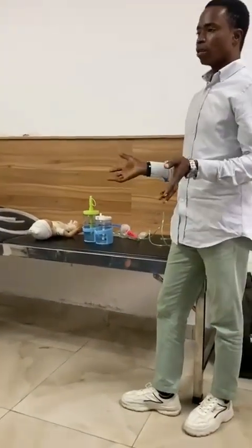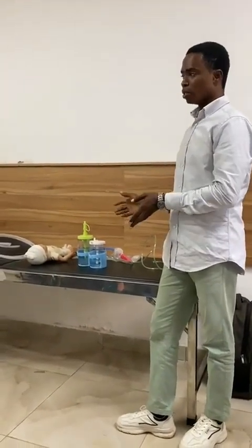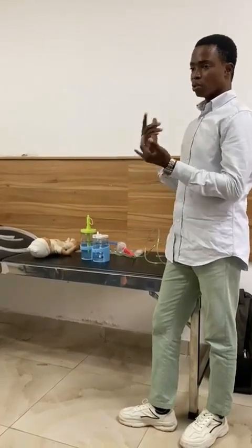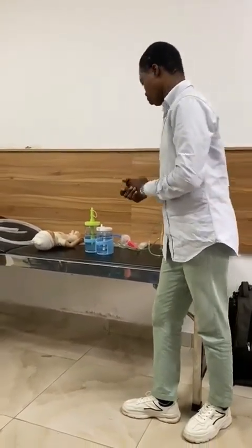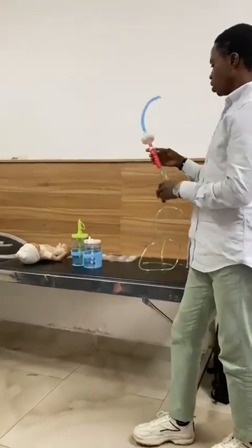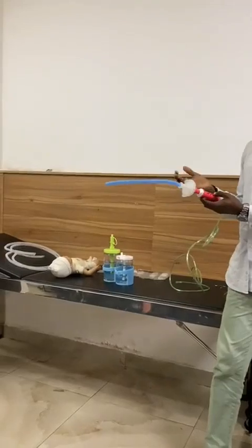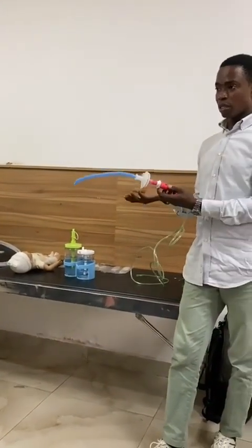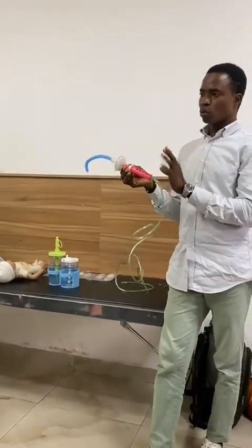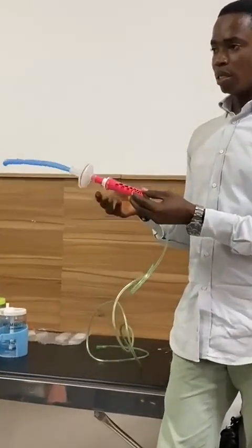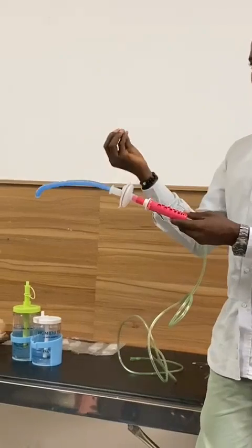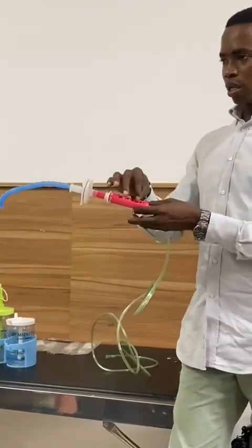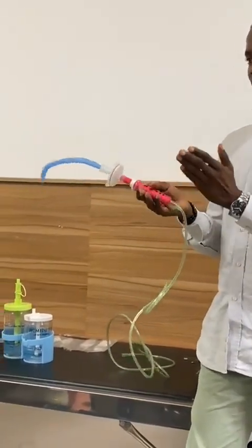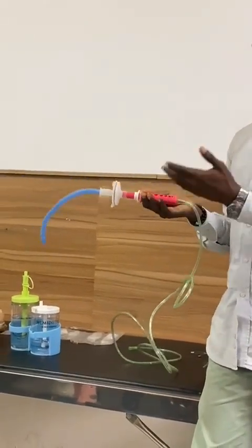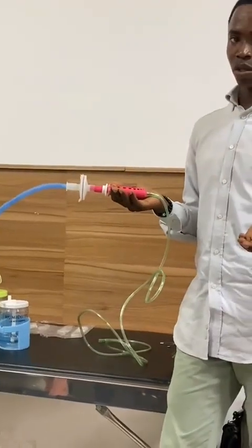As compared to other kinds of CPAP that use electricity and need an air compressor, this does not require electricity. All you need is an oxygen source. You can use an oxygen cylinder or an oxygen concentrator. What makes it unique is the blending system. You all know the components of a CPAP system; it needs a blending system. So it uses what we call a Venturi system to extract air from the environment and mix it with your oxygen source. Then it balances it and determines which FiO2 you are administering to the patient.